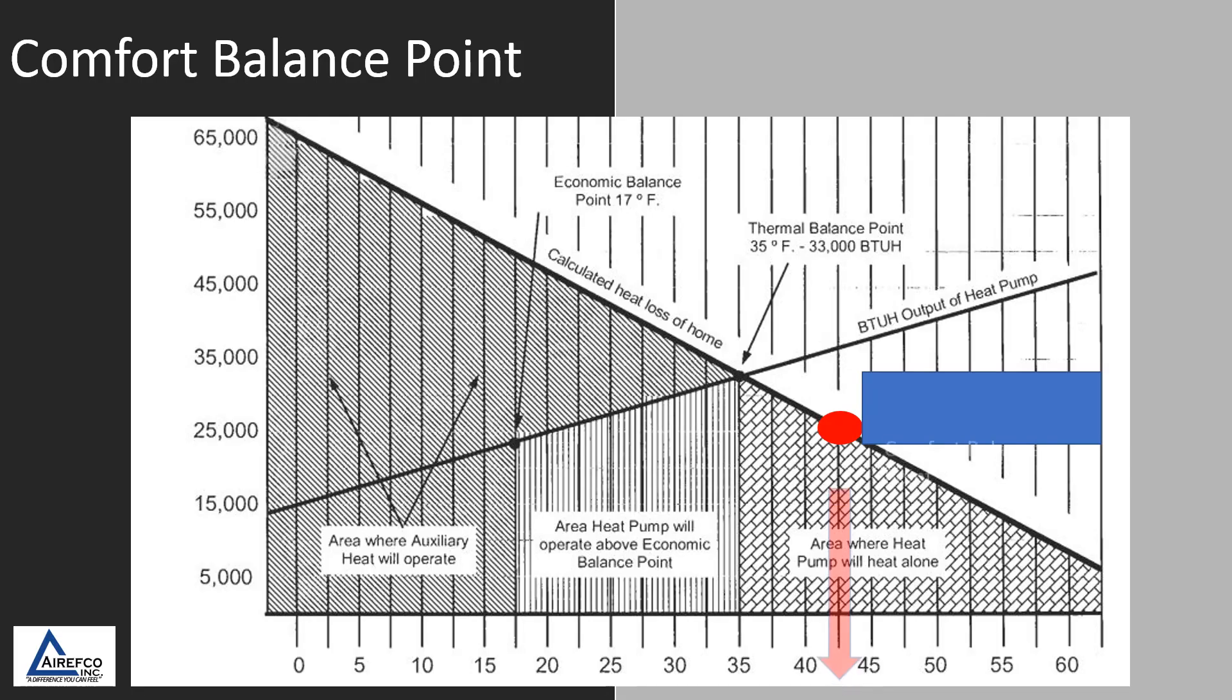The third balance point that you want to take into consideration is the comfort balance point. This point is normally a lot higher than your thermal or economic balance point. You have to take into consideration people who are generally colder than normal, and a normal thermal balance point or an economic balance point would make the house way too cold for their comfort.